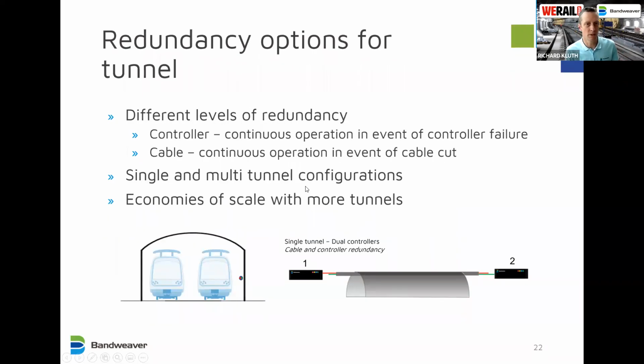So starting with redundancy, with regards to reliability and redundancy, these are critical to the end user. And so typically we find in rail tunnels some level of redundancy is required. And that for this technology can either be at the controller level or at the cable level. So two things. At controller level, you have continuous operation in the event of a controller failure, and at cable level, continuous operation in the event of cable cut or damage.